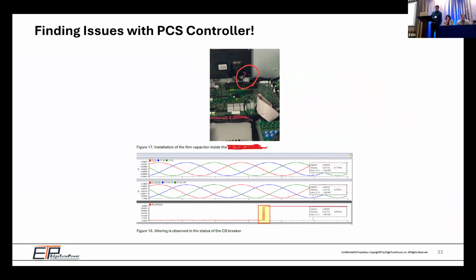So again, why hardware-in-the-loop testing? We were testing the PCS for that project. My apologies if I redacted this part because of the NDA, so I cannot say who the OEM was for that project. But we wanted to test a transition from grid forming to grid following for that PCS. When we were testing the physical controller, we noticed these jitterings. We call it jittering. When you want to switch from GFM to GFL, that was the problem. Believe it or not, the OEM first denied it, and then they said, can you put a cap bank on this terminal here so we can solve the issue? That's something you cannot observe in offline simulation, because you have a model developed of their control system. We have 40 seconds.